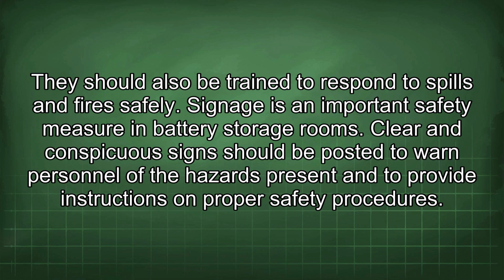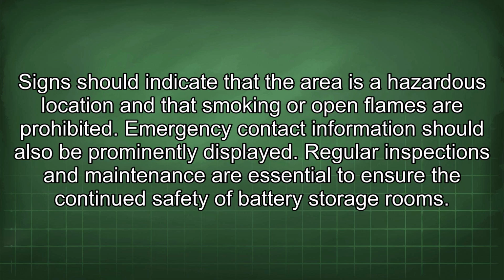Signage is an important safety measure in battery storage rooms. Clear and conspicuous signs should be posted to warn personnel of the hazards present and to provide instructions on proper safety procedures. Signs should indicate that the area is a hazardous location and that smoking or open flames are prohibited. Emergency contact information should also be prominently displayed.